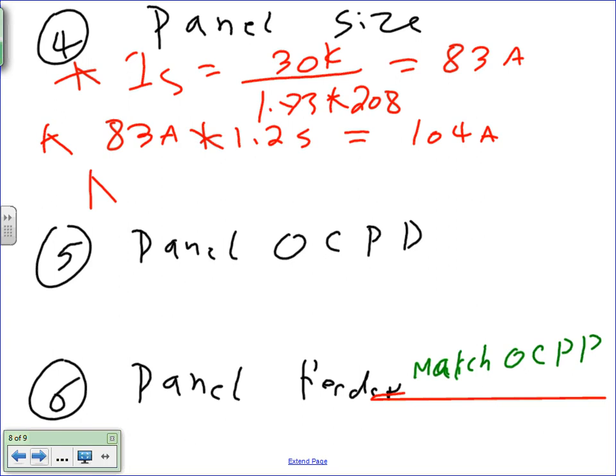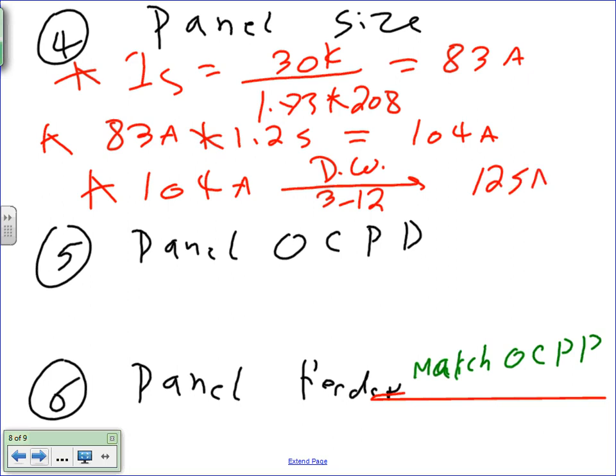And the last step, guys, is to take the 104 amps to the table, 3-12, and what's the standard panel that we need to buy? 125 amp, a 3-phase 125 amp panel. This is the size of the copper or aluminum inside the panel, not the overcurrent protection device.